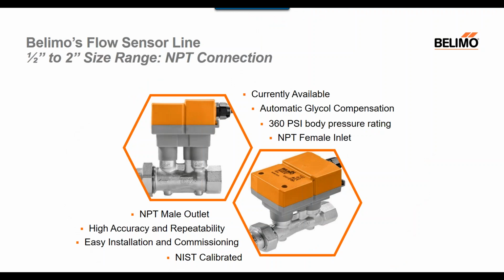So currently available in Belimo's range, what we have today is flow sensors in sizes 1/2 inch to 2 inch models, which all have NPT male outlet and female inlet connections. The smaller sensors are contained in a 360 psi body pressure rated housing and have a very low profile design. And as with all models, incorporate Belimo's patented automatic glycol compensation technology. As well as high accuracy and repeatability, they're also available with NIST Traceable calibration certificates.